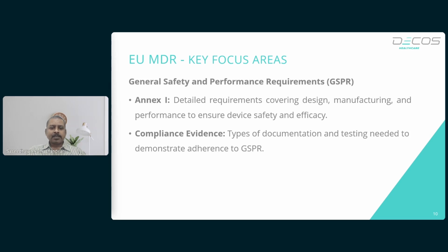The EU MDR's Annexure 1 outlines detailed safety and performance requirements that apply to all devices. Manufacturers must provide evidence through technical documentation, clinical evaluation reports, and risk assessment to show they meet these requirements. The Annexure 1 of EU MDR covers device design, manufacturing, risk management, and labeling. It ensures devices are biocompatible and safe for use.